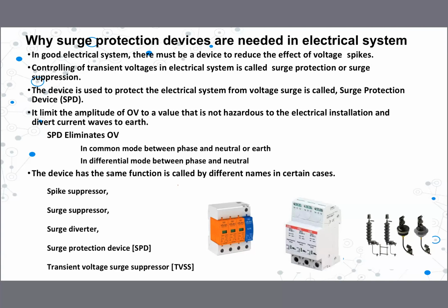The device we use to minimize or cut off or eliminate the transient voltage is called a surge protection device. In easy terms, we call it SPD. All of you have heard of SPD. So in most of our electrical systems nowadays, we have SPD. What it does is limit the amplitude of the overvoltage to a not hazardous level, right? Sometimes it does not bring it down to zero, just to a not hazardous level. Later in our discussion, let's try to understand what is hazardous and what is not hazardous, right?